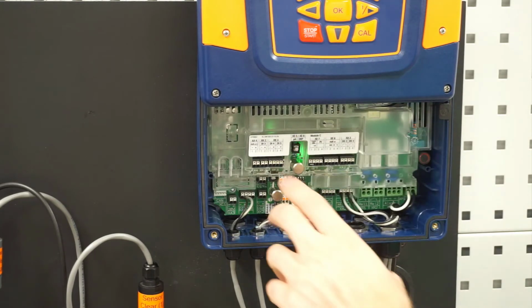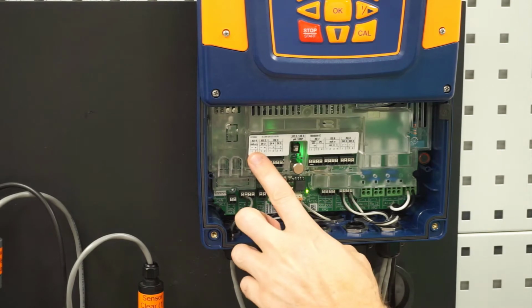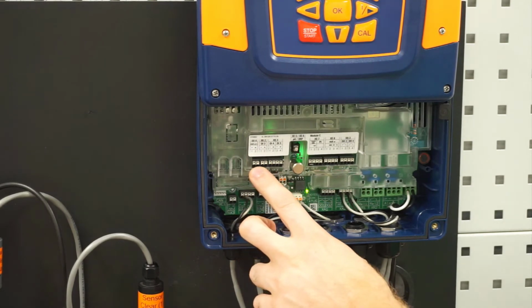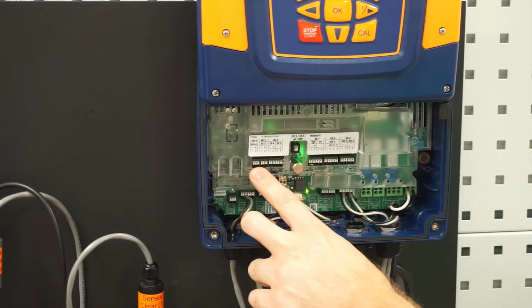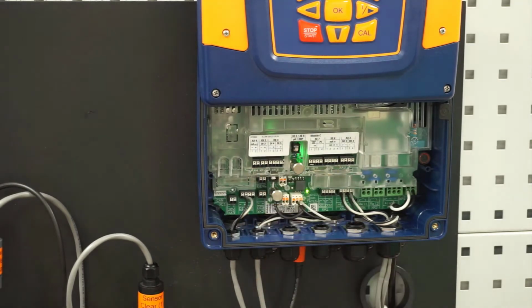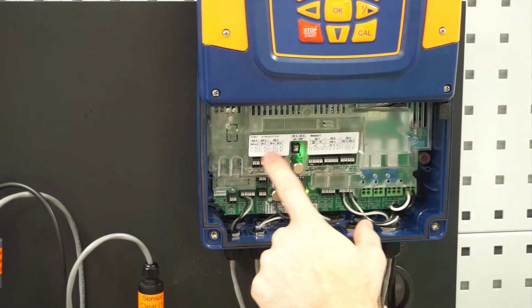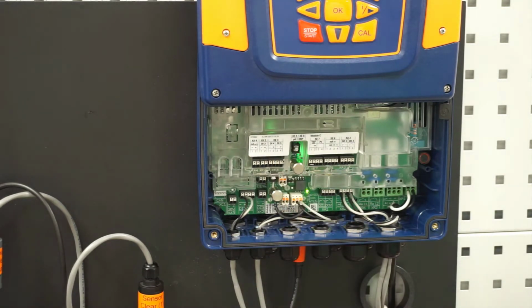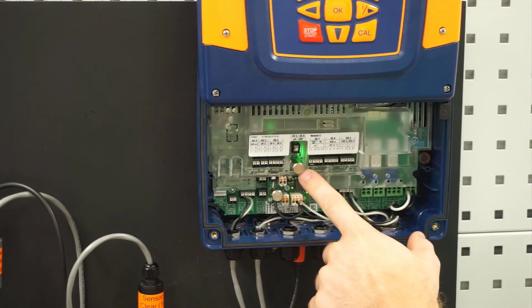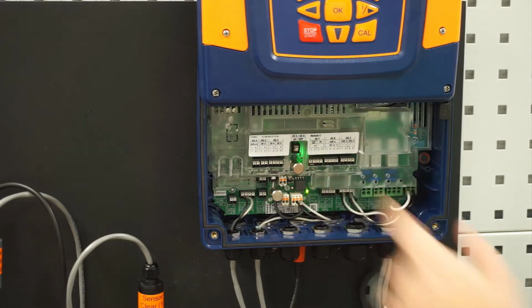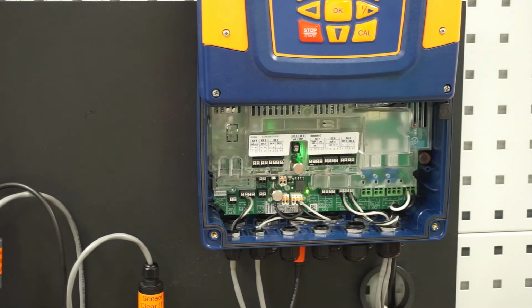Going up top, we have an additional milliamp output. So that's milliamp output 3. We do not wire that from the factory. You have the option to use that if there's something else you would like to output. Next to that, we already talked about our digital inputs. On this top board, we have an additional spot to put a pH or ORP sensor. We're not utilizing that in this case, but it could be added on site. It is unlocked. It is ready to go.